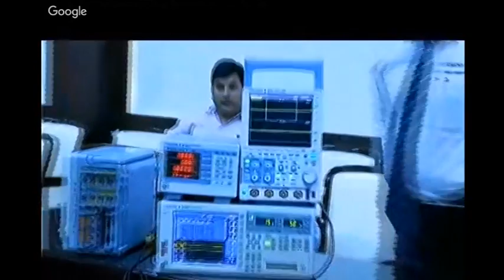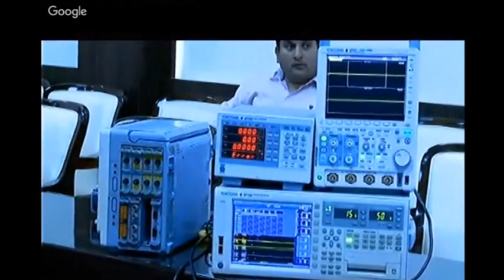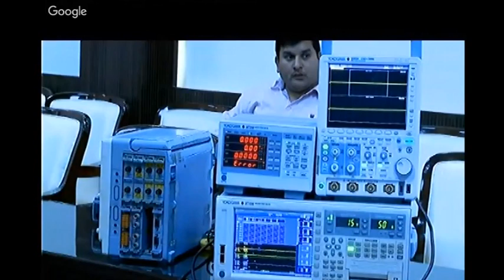If you see the right side panel of the equipment, it has 8 slots which can accommodate 8 modules. So it's a modular platform, and you can choose the module based on your application requirement, either voltage, current, acceleration, strain, frequency, temperature, whatever it is.